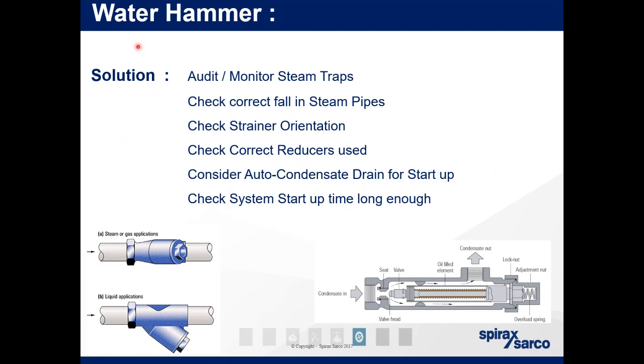So again, here the solution: audit and monitor steam traps. So checking your steam traps, making sure they're working correctly. Correct fall in the steam pipes, as we said, that 1 in 100. Check strainer orientation, referring to here. So you've got one for steam or gas applications and then liquid here. Check correct reducers. So let's talk about the eccentric and the concentric. Consider auto condensate draining for startup. So that would be this trap here, which I will touch upon after the last point. And check steam system startup time is long enough. So are you giving your system long enough to warm up before you start opening those isolation valves?